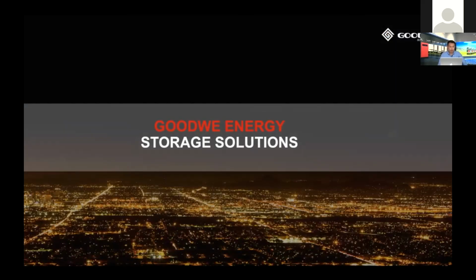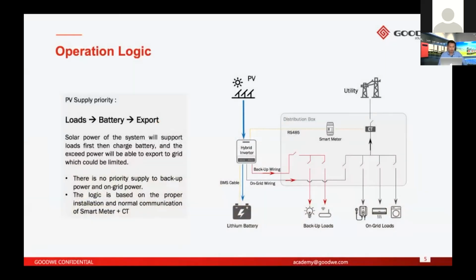Now we will start with the operation logic of hybrid systems. Here we just take a hybrid system as an example. Actually, for AC coupled and on-grid inverters together, the logic is almost the same as hybrids. There are two basic logics. The first logic is if the PV power is enough, it can charge the battery, support loads, and export to the grid.